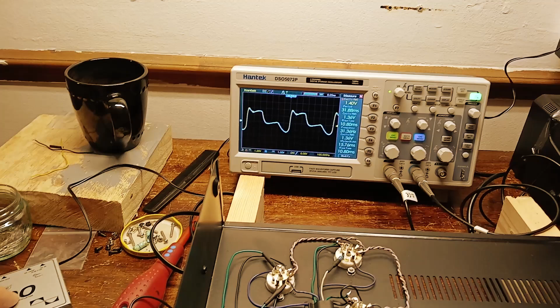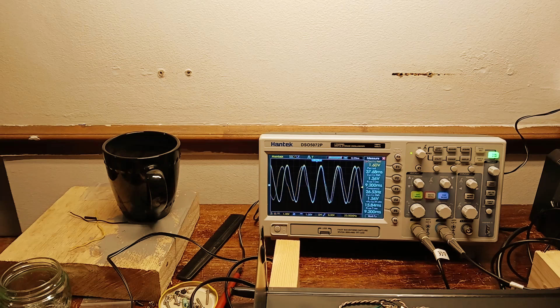Ooh, it doesn't like that, does it? What's its lowest frequency? It's happy with it at that level, 59 hertz by the looks of it. You get below that and we start seeing some... ooh, look at that. That is transformer saturation, so you're seeing harmonics manifesting as sum and difference frequencies. If you did a Fourier transform you'd see loads of various order harmonics from that. So about 50 hertz, that's 2.12 and 2.2 volts.